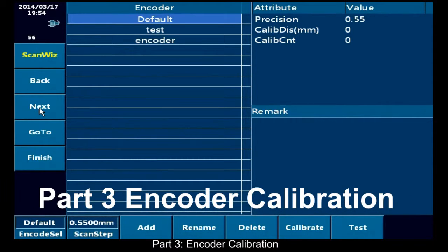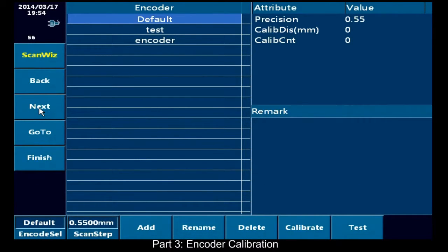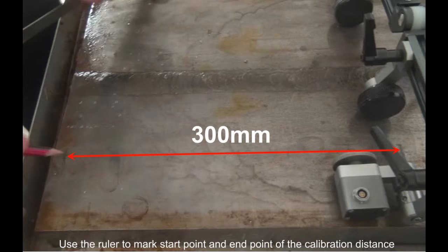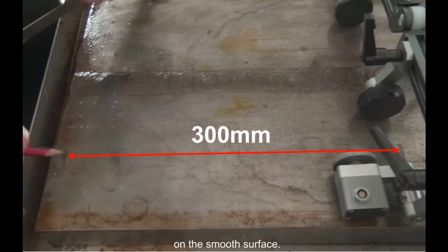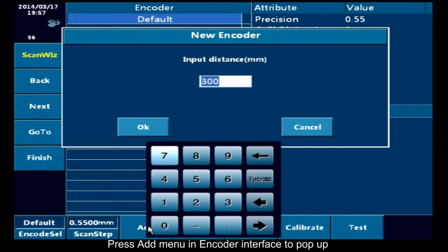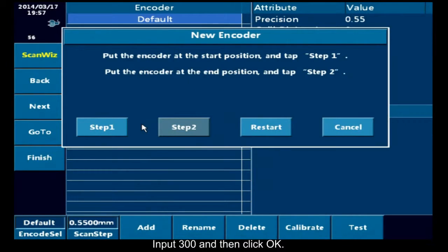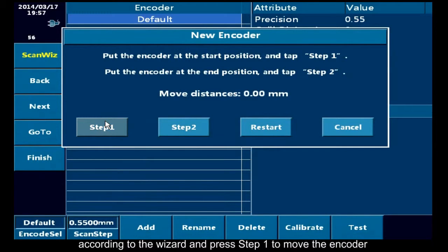Part 3. Encoder calibration. The distance to be calibrated is 300 mm. Use the ruler to mark start point and end point of the calibration distance on the smooth surface. Press Add menu in Encoder interface to pop up the new encoder calibration distance window. Input 300 and then click OK. Place the encoder at the start position of calibration according to the wizard, and press step 1 to move the encoder to the end position of the calibration.